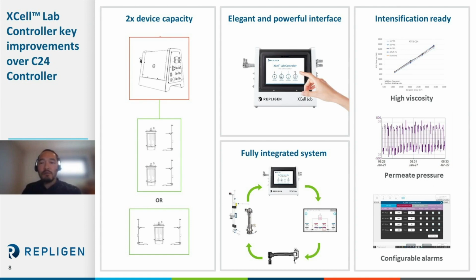First of all, the new XCell Lab controller is available in a dual channel configuration, meaning one controller can control two different ATF devices. You can see that in one configuration, two devices are connected to separate bioreactors. The ATFs connected can be the same, for example, both being ATF1s or both being ATF2s, or they can be different, one being ATF1 and one being ATF2 or 4. So you can really mix and match depending on your bioreactor size and working volume. The configuration below that shows two ATF devices connected to the same bioreactor. This can be helpful when mimicking a process that requires two ATFs at large scale, for example.